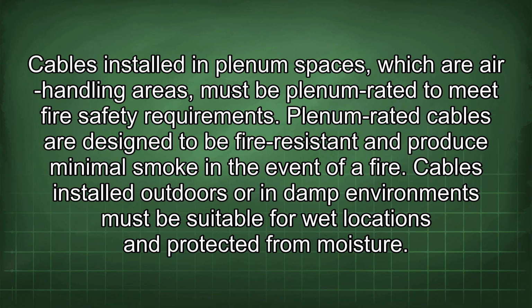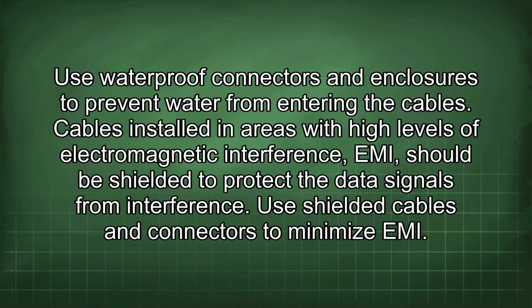Plenum rated cables are designed to be fire resistant and produce minimal smoke in the event of a fire. Cables installed outdoors or in damp environments must be suitable for wet locations and protected from moisture. Use waterproof connectors and enclosures to prevent water from entering the cables.